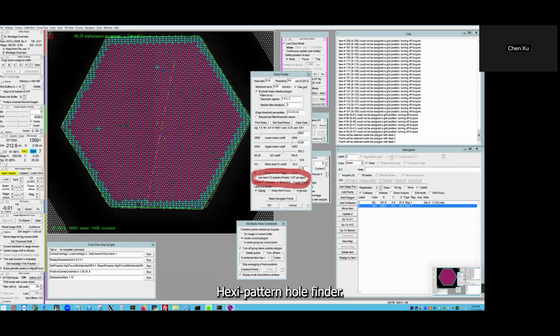Then you define a pattern. Define the image shift pattern by clicking these big buttons in the middle using the hole finder. Hole combiner, then you combine them into a few stage positions. So here I will show you the example with 5 layers of holes, a big spacing pattern. The maximum shift is 5.1.